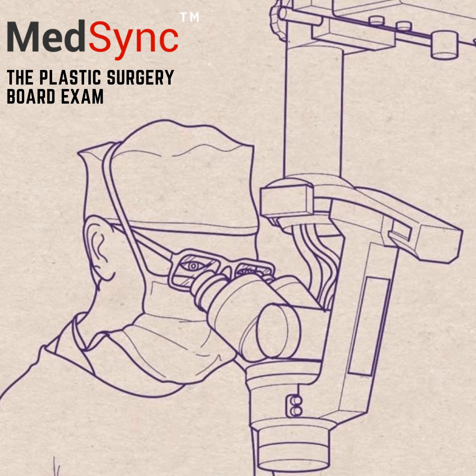And what happens to the implant itself? The explanted device cannot be thrown away in standard biohazard waste. And you certainly cannot let the patient take the implant home as a morbid souvenir. Yeah, please don't do that. It must be treated as a biohazard, securely packaged, and returned to the manufacturer. Why the manufacturer? The manufacturer is legally obligated to collect the implant, perform rigorous analysis on the shell and the biofilm, and provide their findings in a formal vigilance report to the authorities. They are on the hook to investigate.